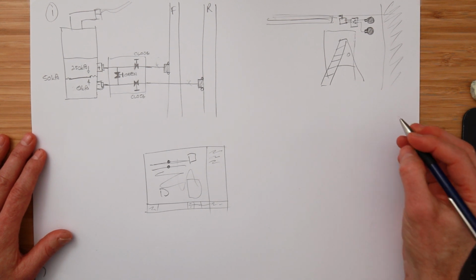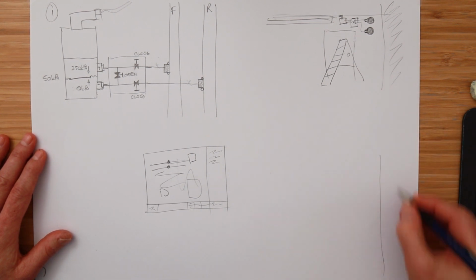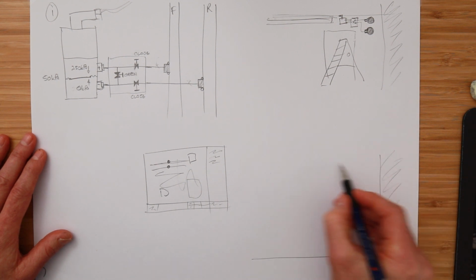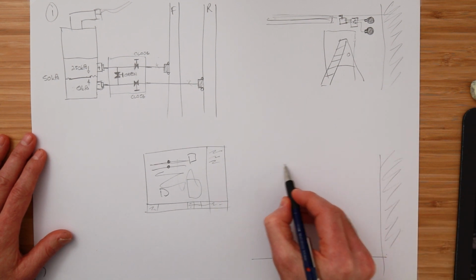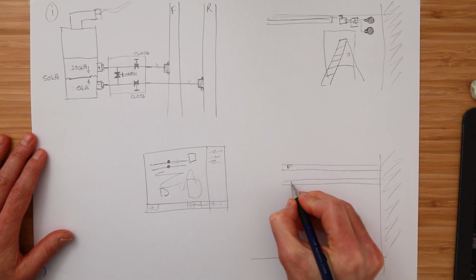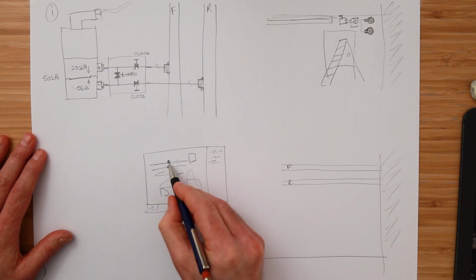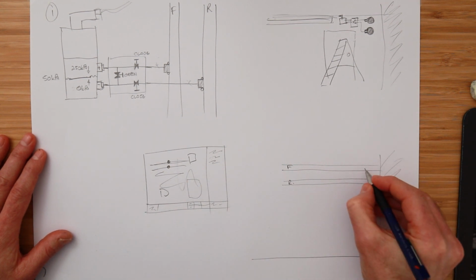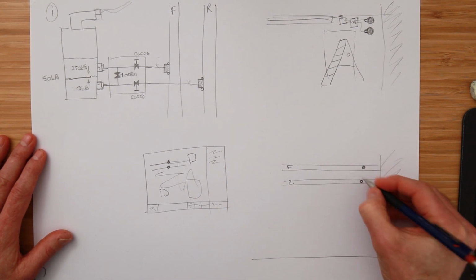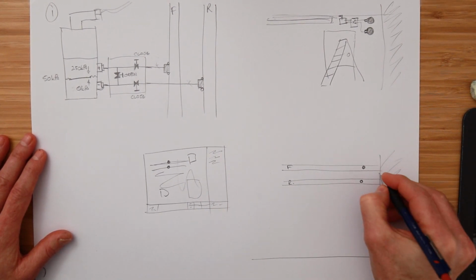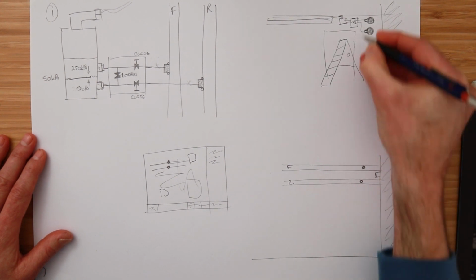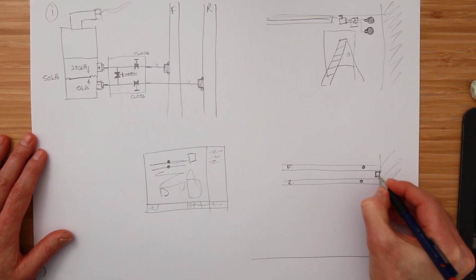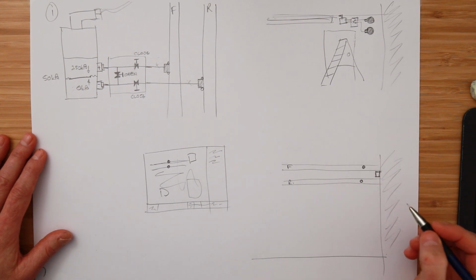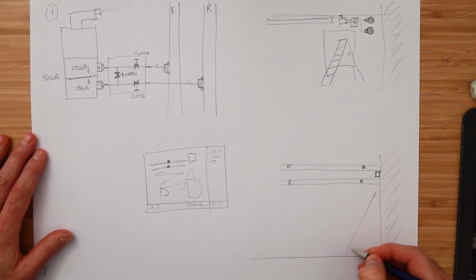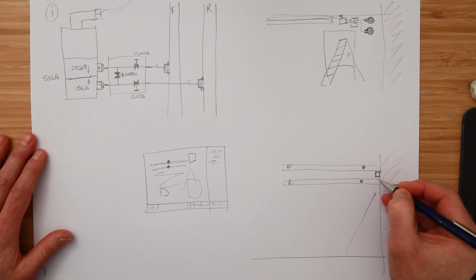Another thing that can happen is, let's say, here's the wall again in the plant room, and it's like a side view. Here's the flow pipe. Here's the return pipe. And on your schematic, this was a good location, and that good location, maybe it's over here. So mechanical welds the socket in here. That's all they pretty much do. And then your installer comes along, and again, he puts the transmitter on the wall over here. It's sort of like this, I guess. Here's the transmitter installed on the wall. It's a good location. But again, the service technician needs to come here with a ladder, get up the ladder. So we're working at heights unnecessarily.